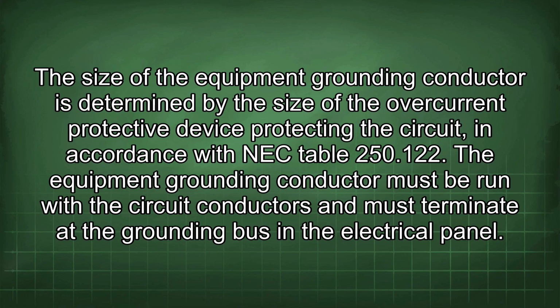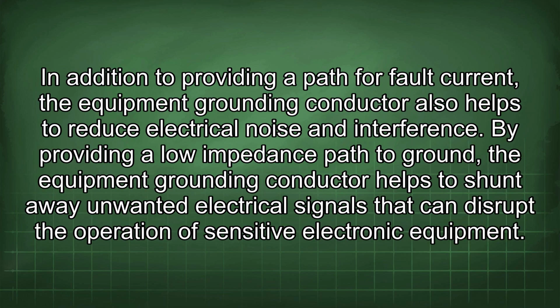250.122. The equipment grounding conductor must be run with the circuit conductors and must terminate at the grounding bus in the electrical panel. In addition to providing a path for fault current, the equipment grounding conductor also helps to reduce electrical noise and interference. By providing a low impedance path to ground, the equipment grounding conductor helps to shunt away unwanted electrical signals that can disrupt the operation of sensitive electronic equipment.